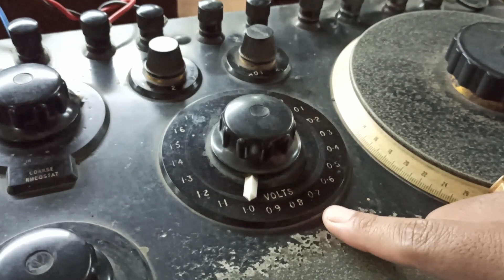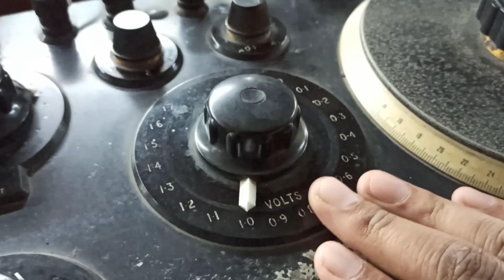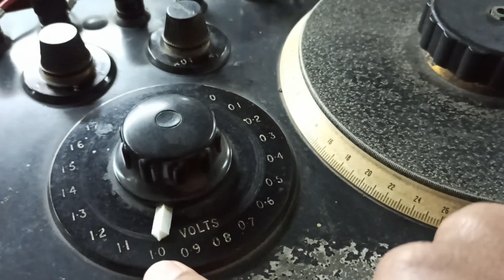So when we get the null point, we need to note the value of these two slide wires. As you see, this is the main slide wire and the value is 1, and this is the vernier slide wire. By this pointer we can see this is at 39.2, and this has a multiplication factor of 1 by 1000. So by multiplying this factor and the range, we will get the actual value. So the total value will be main slider plus vernier slider into range.